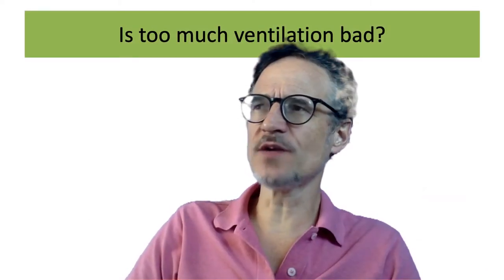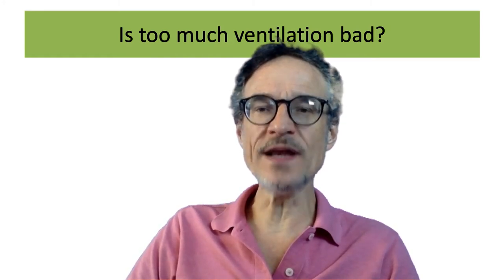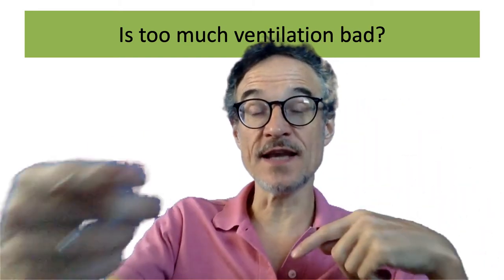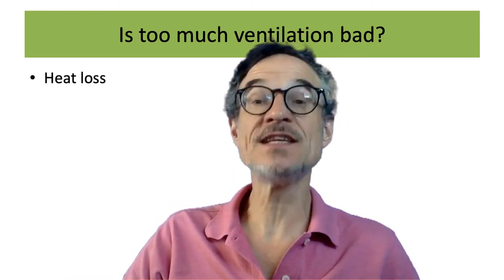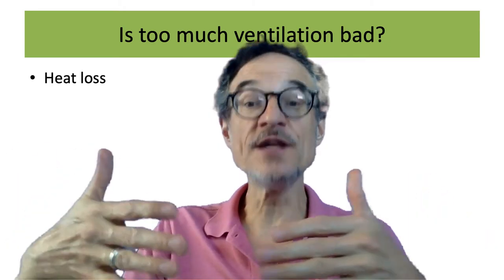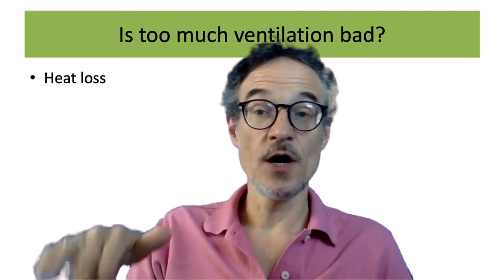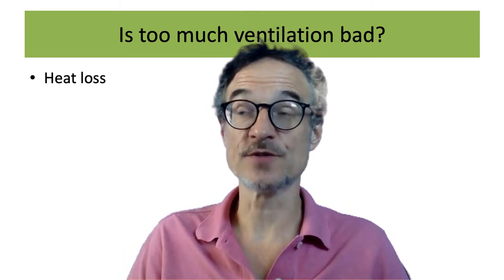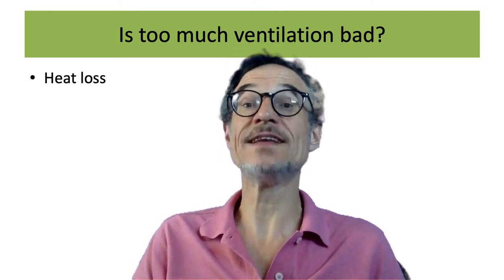Is too much ventilation bad? Remember that if it's winter and it's warm inside, we have lots of nice warm air. As we're ventilating, we're losing all of that air. So one reason too much ventilation is bad is heat loss. As a house gets better insulation and we lose less heat through the walls, the heat we lose through ventilation becomes a bigger part of our total heat loss. So for a low energy building, we need to think about heat lost through ventilation.